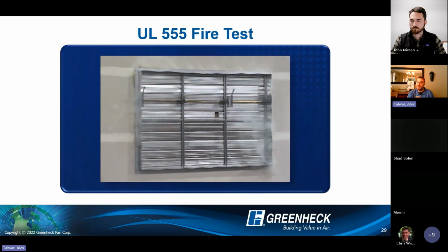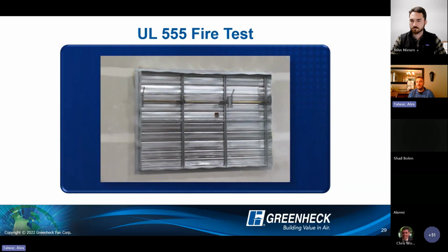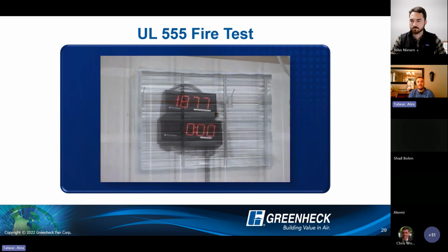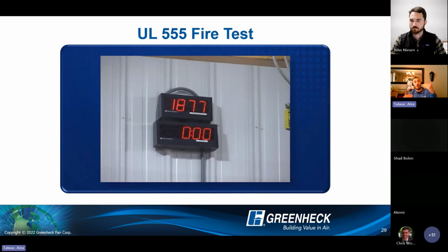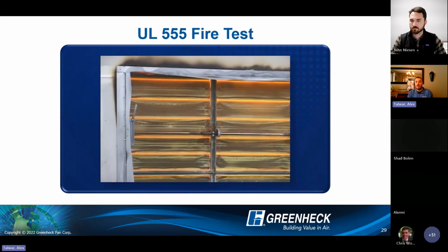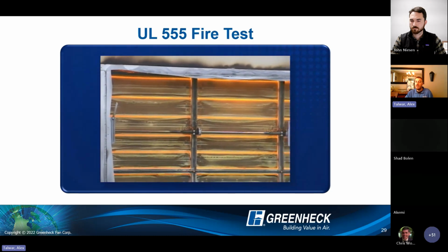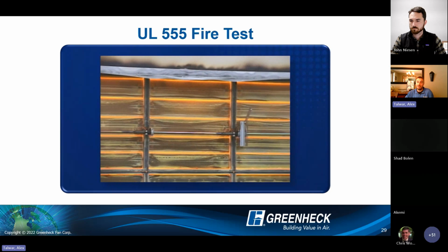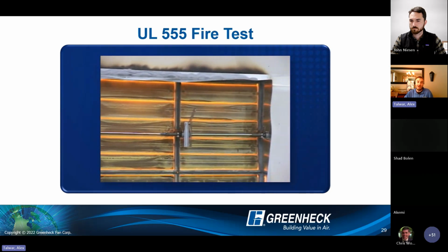So we start at ambient and ramp up to 1,000 degrees in the first 5 minutes of the test. We start with the damper in the open position, let the heat response device, the fusible link, activate and close the damper, and then stand back and watch it burn, essentially, for 1.5 hours or 3 hours.